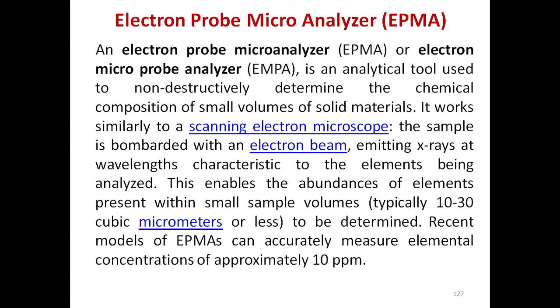The sample is bombarded with an electron beam, emitting X-rays at a wavelength characteristic to the elements to be analyzed. This enables the abundance of elements present within a small sample volume to be determined, typically 10 to 30 cubic micrometers or less. Certain models of EPMAs can accurately measure elements at a concentration of approximately 10 ppm, that is parts per million.